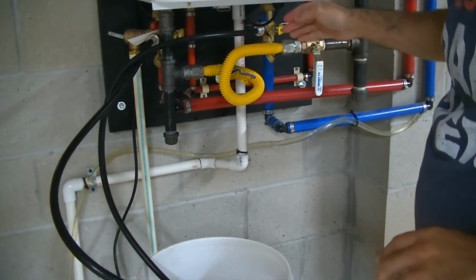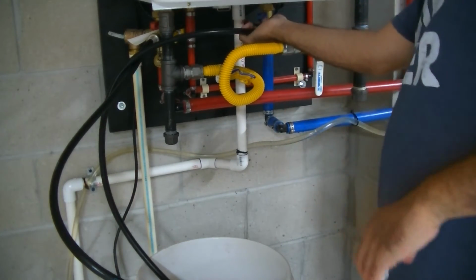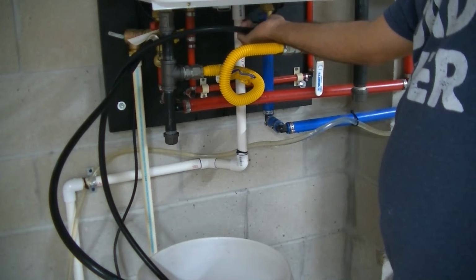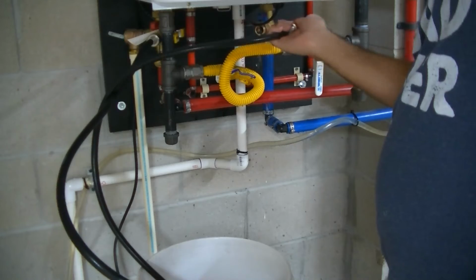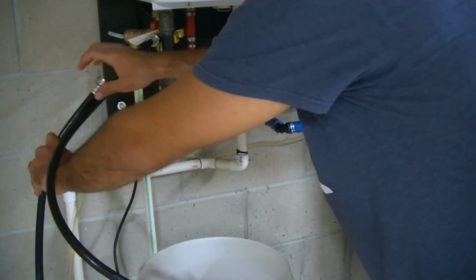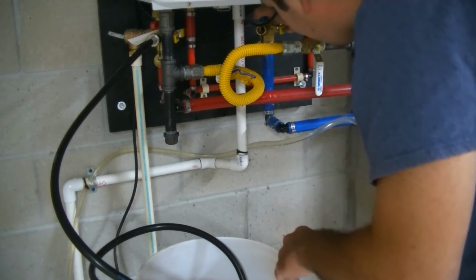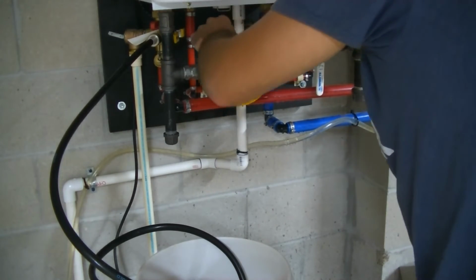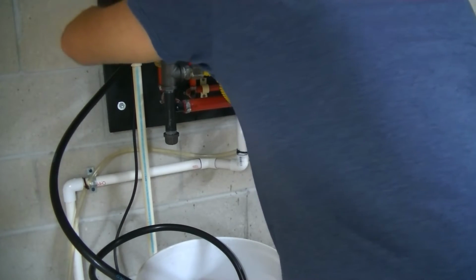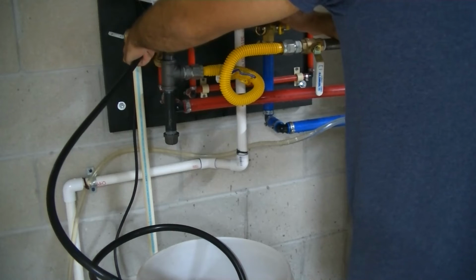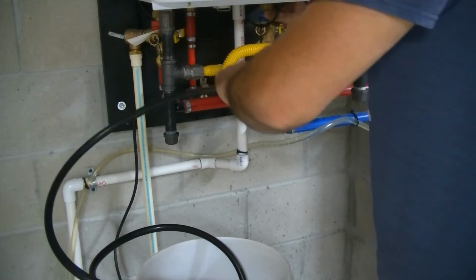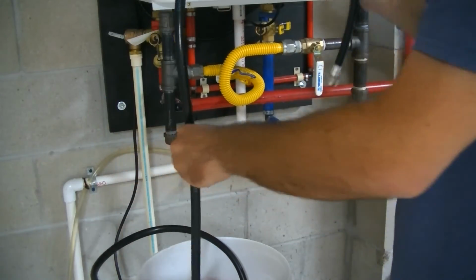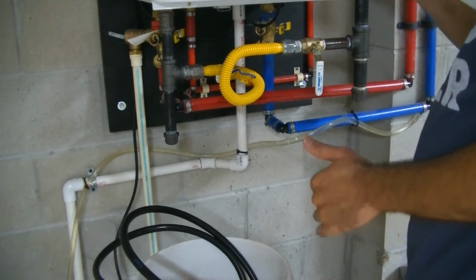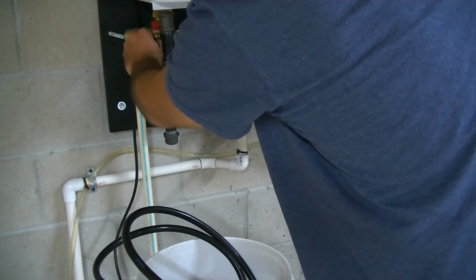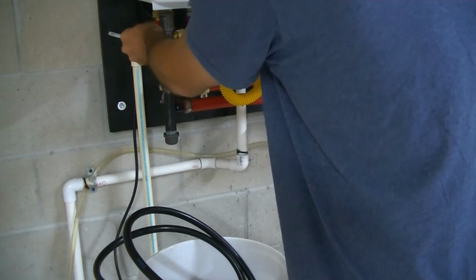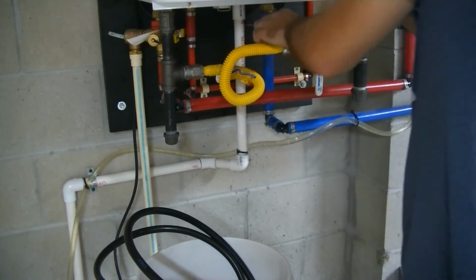Now we're going to disconnect our hoses. These were only finger tight, so we shouldn't have an issue. We're going to turn these valves off so they stop dripping, and pull this one off. Now that we got those off, we can put our caps back on - these copper caps are service ports, finger tight, you don't have to kill them. Same thing on this one.